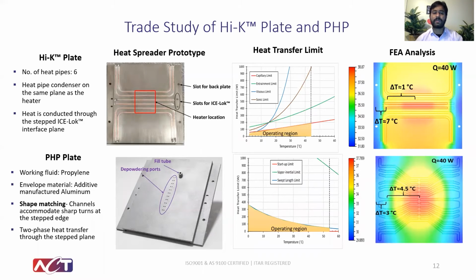Before the performance testing, we did a trade study of the high K plate and PHP heat spreaders to determine the heat transfer operating limits and also to predict the performance via FE analysis. Now for both the high K plate and PHP, the heat transfer limit we determined was more than 100 watts up to 44 degrees C operating temperature.